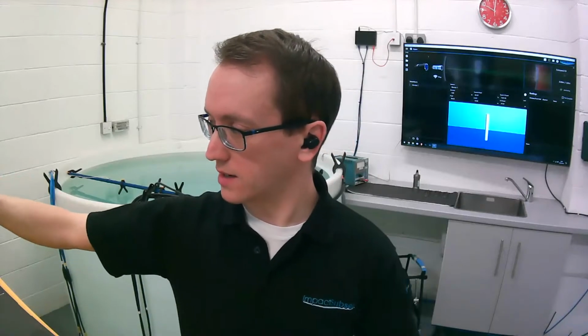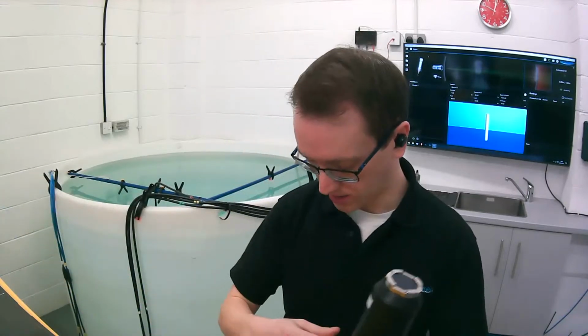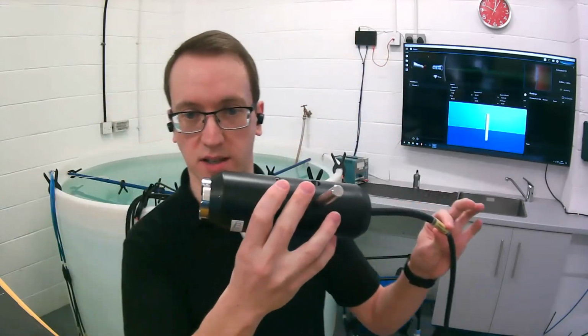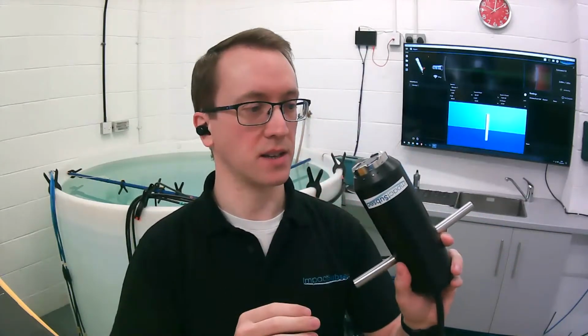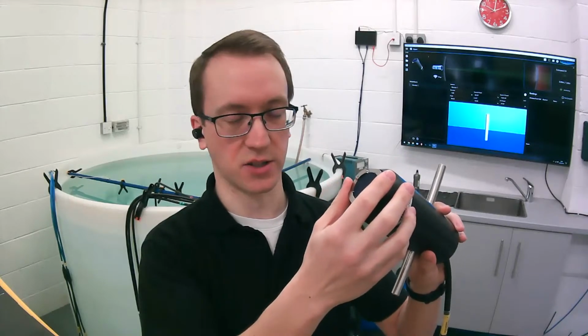So it's important to regularly go around subsea structures and check them to make sure they haven't flooded. And there's a number of different ways of doing this. There's a radioactive source method, a gamma ray method, and then there's the use of acoustics, which is the type of system we provide with the IS-FMD system. Our flooded member detection system is based around a single probe. That's the probe in its housing there. It's based on the ISA 500 sensor at its core.